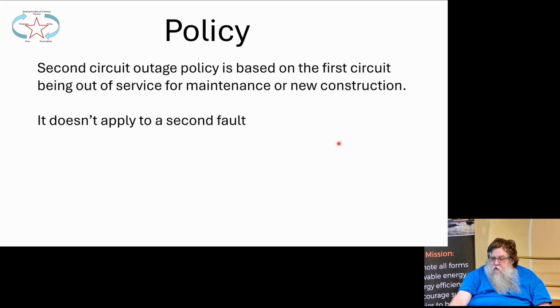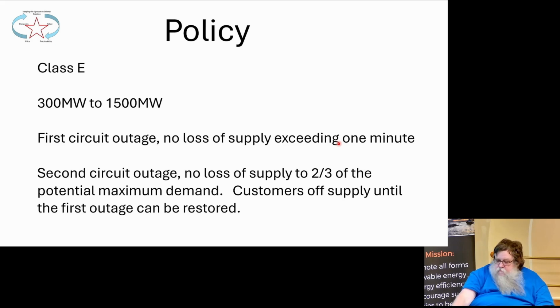Oh, right. It doesn't apply to a second fault. So this second circuit outage does not apply if you've got two faults at the same time. And then just for completion, Class E, first circuit out, above 300 megawatts to 1500 megawatts. First circuit outage, no loss of supply exceeding 1 minute. Second circuit outage, no loss of supply to 2/3 of the potential maximum demand. Customers are off supply until the first outage can be restored. That's what the rules say.